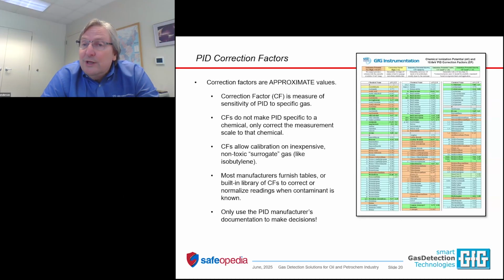PIDs are providing readings that are relative to the gas used to calibrate the PID. But if you want, you can make the reading specific to the gas of interest. And the way you do that is by choosing a correction factor. The correction factor is what the instrument will use to multiply the actual reading to come up with the true concentration. In most PID-equipped instruments, you have an extensive library of correction factors. So if you know that you're dealing with toluene, you can simply choose toluene from the library, and your reading will be, actually it's not going to be that much different than the reading for isobutylene scale. But you can choose the toluene scale and it will exactly calculate the reading for toluene in true toluene increments or units of measurement.